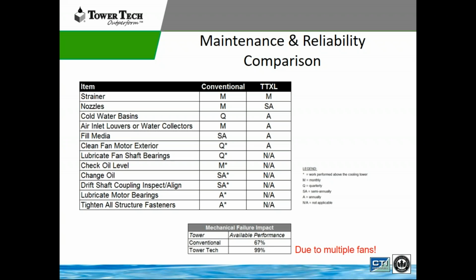From a maintenance and reliability comparison, strainers, obviously monthly on both systems, nozzles, monthly for the conventional system. Our nozzles, they call them a non-clogging nozzle, but we recommend you inspect them semi-annually. Cold water basin, conventionally quarterly, we do it annually. Air inlet louvers or water collecting systems, they do it monthly, we do it annually. Fill media, semi-annually, we say annually. And then clean fan motor exterior, they're quarterly. Now they have a gear system, okay? We have direct drive fans, so we're doing it annually.